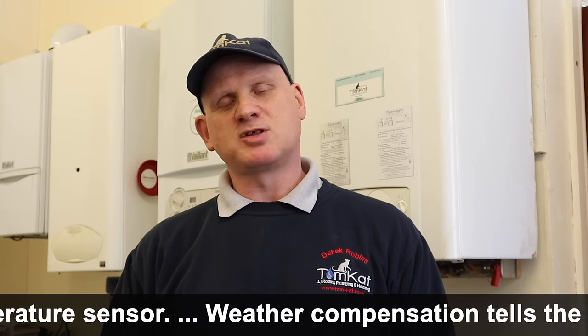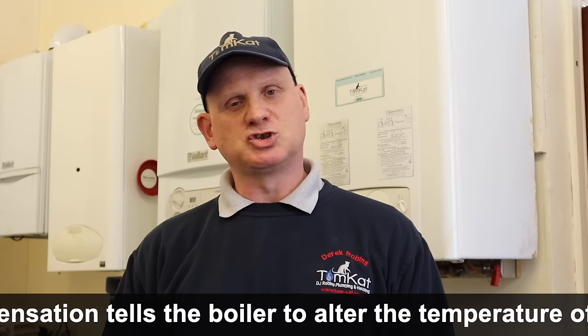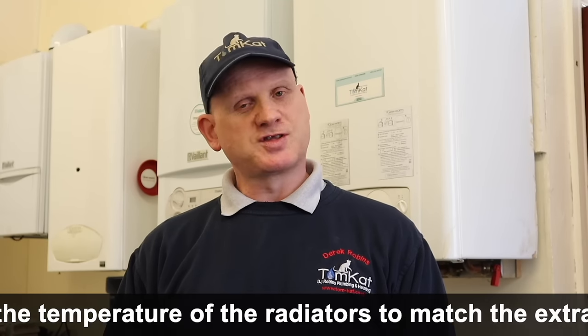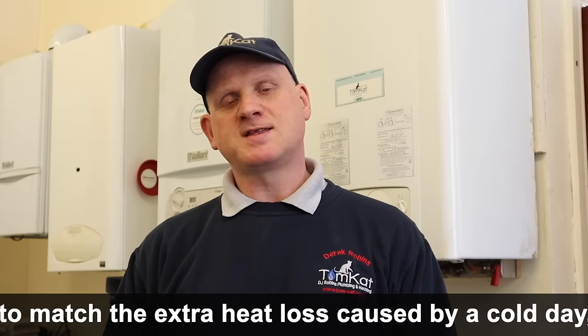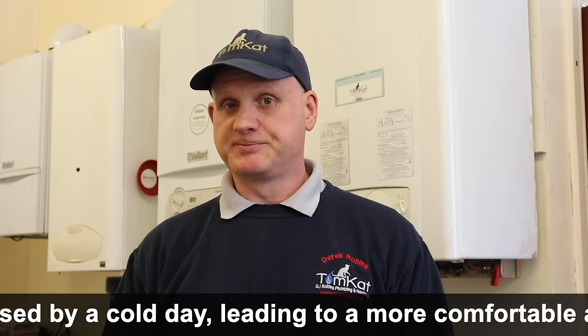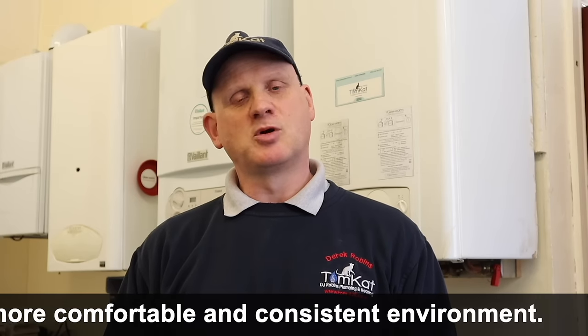Most smart thermostats use weather stations to be able to achieve this. Weather compensation adjusts the boiler up and down as the outside temperature goes up or down. It makes the boiler incredibly efficient, but the controls also speak the language of the boiler. So we have a situation in the UK where most smart controls are not set up to speak the language of the boiler. Like I say, the best option for the customer and the best option for the engineer is to always install the controls laid down by the manufacturer of the boiler. It makes it a lot easier to install, and a lot easier for the customer to work.